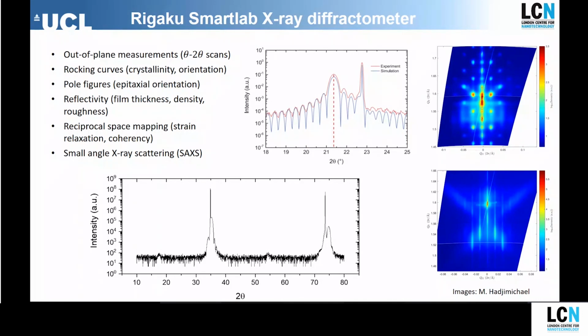So you can do the standard out-of-plane measurements. Here all of the examples are for thin films, but of course you can also do it on powders and samples in capillaries. So you can do these theta-2theta scans for determining the lattice parameters and the film thicknesses if you have films of very well-defined thickness. You can do rocking curves for crystallinity and mosaicity of your samples, pole figures for epitaxial materials to determine textures and orientation of your samples, reflectivity for film thickness and roughness, and reciprocal space mapping.